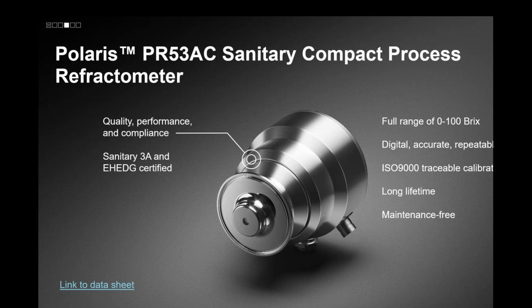That is sort of a trust coefficient, if you will. What does the signal look like? Is it trustworthy or not? It's not so much a number that you need to be worried about as a number itself, but if you see it starting to slip from a high number to a low number over time, that could mean that you're getting a coating and you need to pull the sensor for cleaning or do something else.